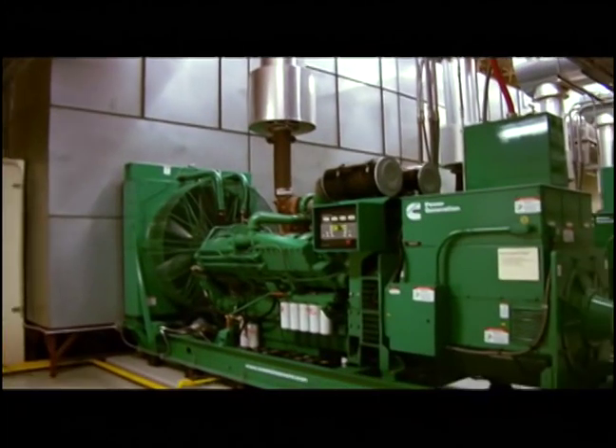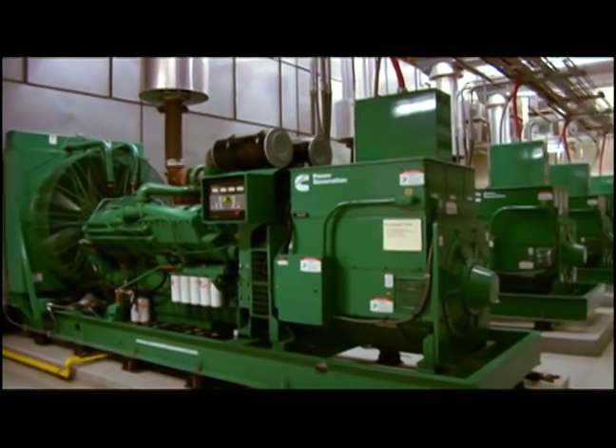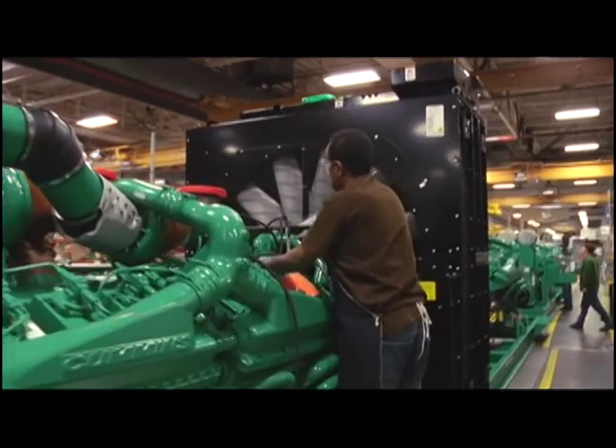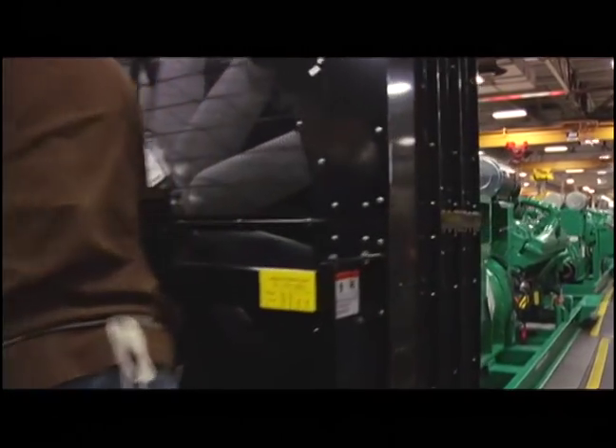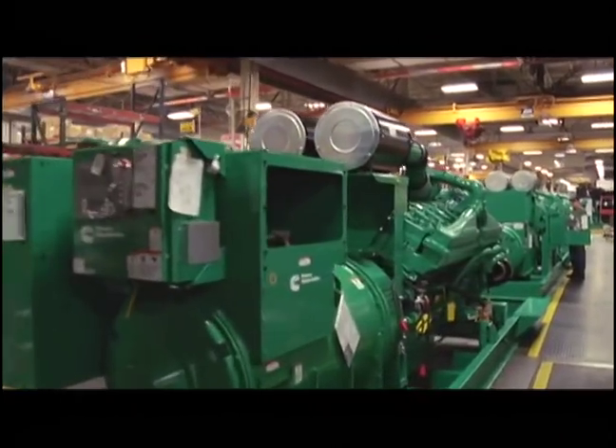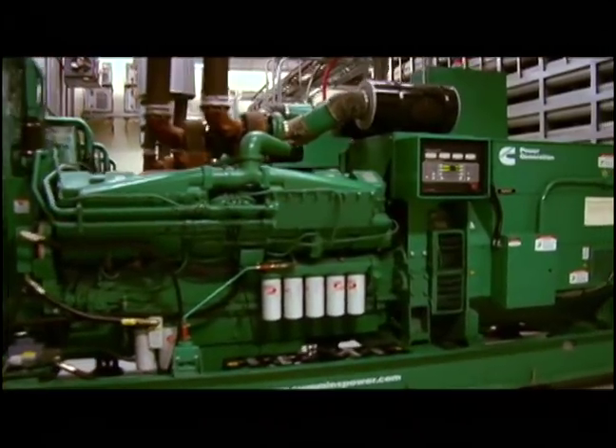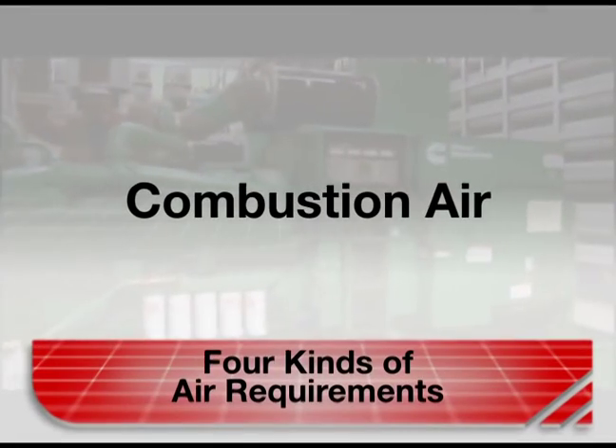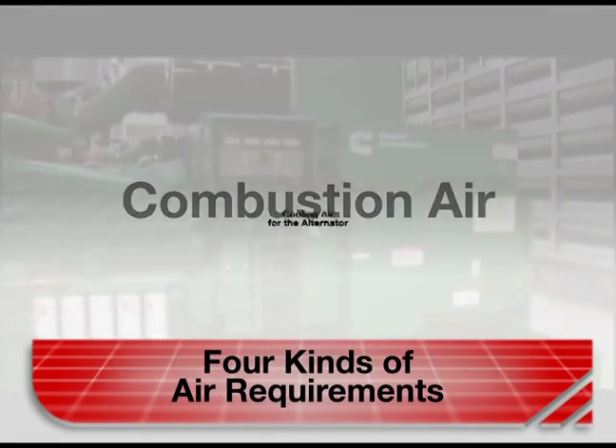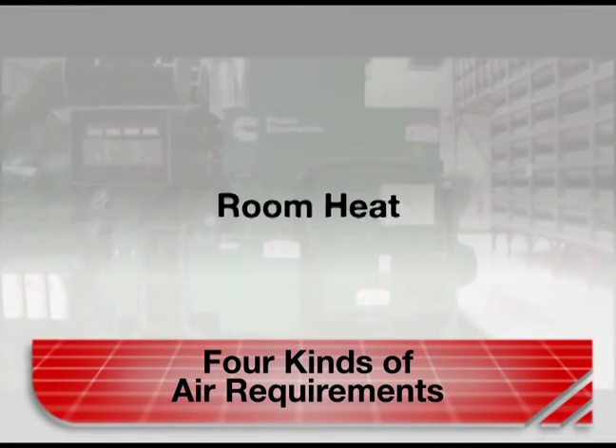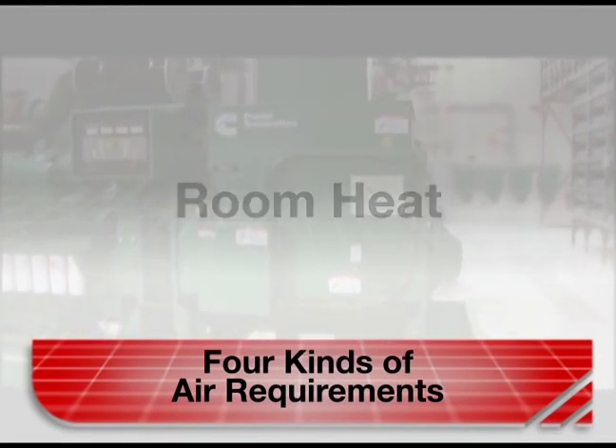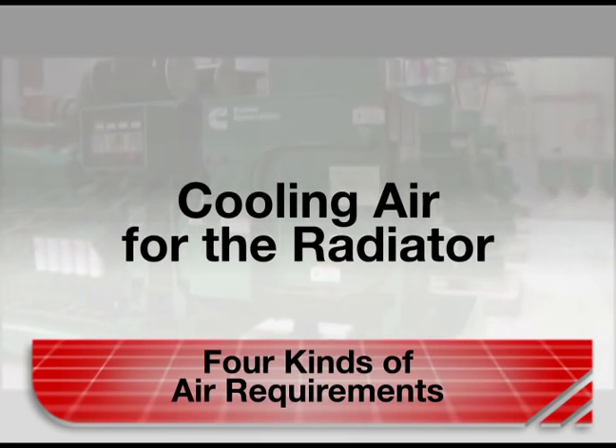This can be very misleading. In contrast, Cummins provides cooling systems well suited to the generators they are paired with, to account for all four kinds of air requirements: combustion air, cooling air for the alternator, room heat, and air to cool the radiator.